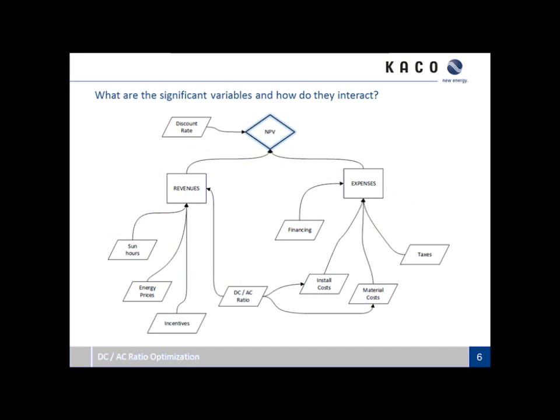This thought map captures the top-level interactions of how variables affect net present value. You have the discount rate shown in the equation earlier. Revenues for a PV system are driven by sun hours, energy prices in dollars per kilowatt-hour, and incentives — either dollars per kilowatt-hour or dollars per kilowatt for capacity-based incentives. On the expense side: financing, taxes, material costs, and install costs. Behind all of this is DC to AC ratio — increasing it can increase energy harvest and revenues, but it also increases installation costs, land, labor, and material costs for inverters and modules.